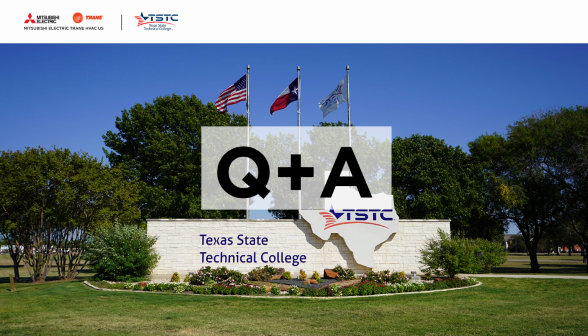We set it up where we give them probably a 4-degree temperature range from 68 to 72, depending on the time of year and the temperature outside, for the students to control. We do monitor the energy in the building, but we don't monitor the energy use by room. We try to have energy efficiency in every way that we can, through things that won't affect the students as much. We have some lighting controls as well, but we just give them a narrow range of temperature to go to. That's how we manage what the students use.